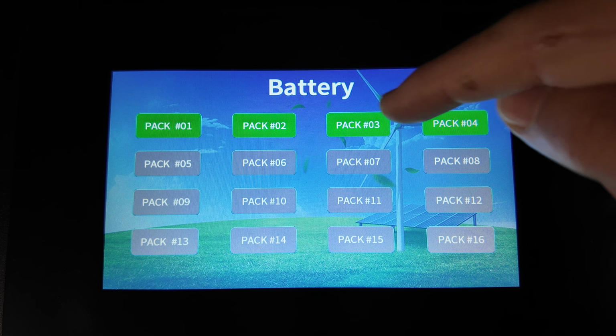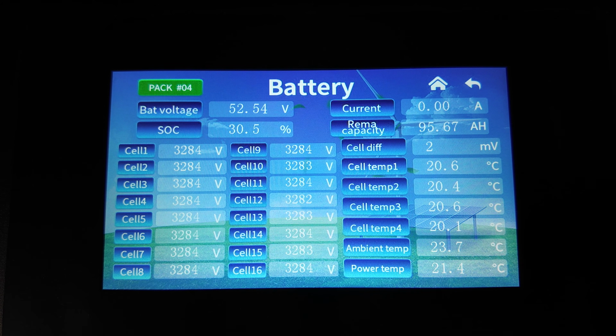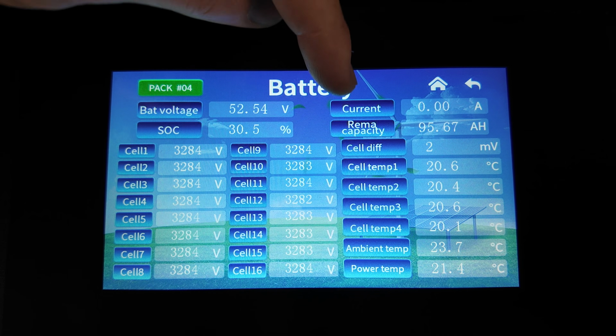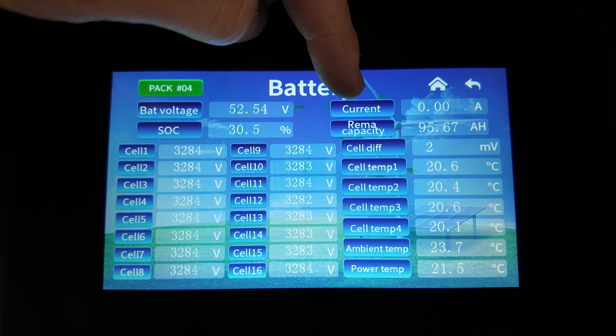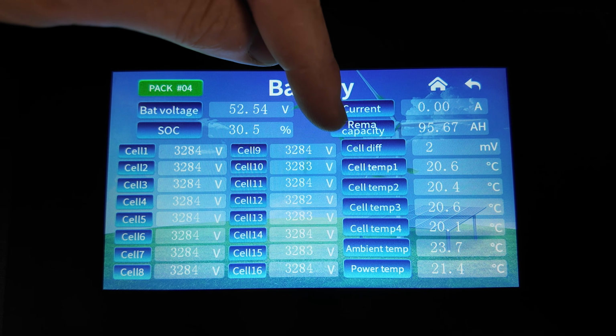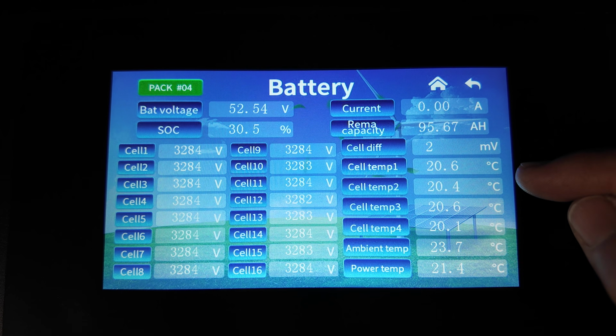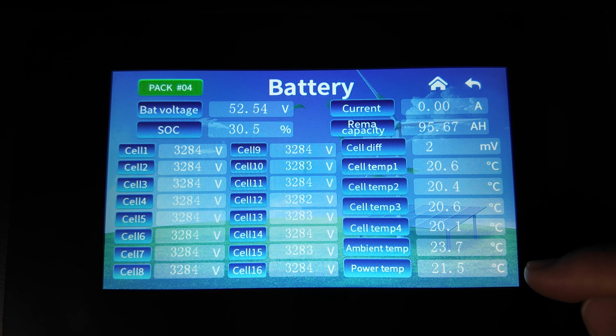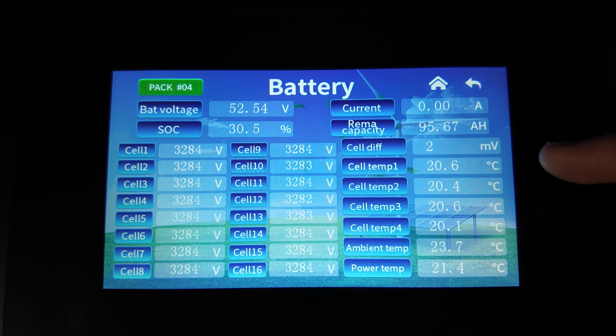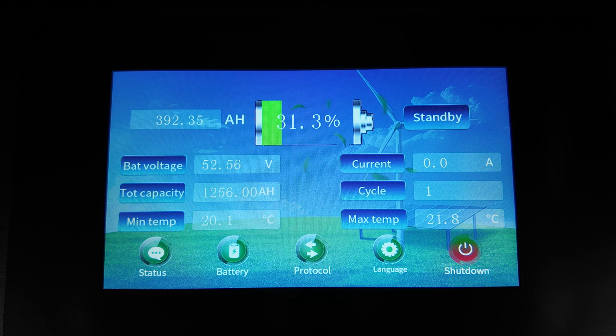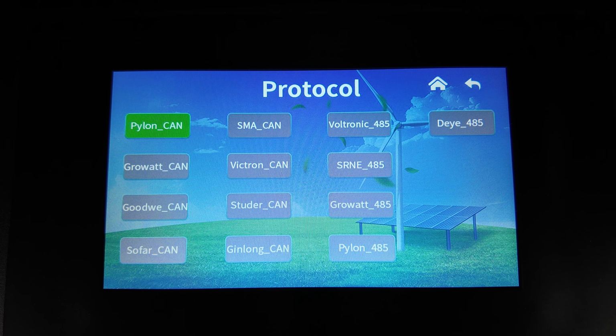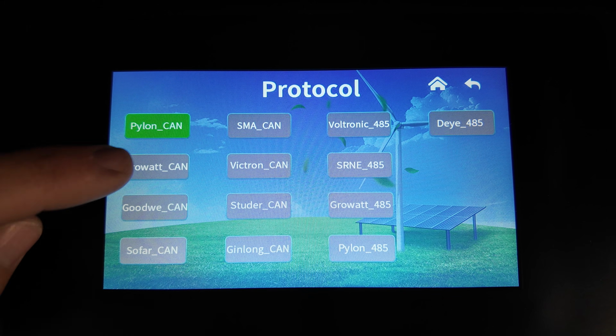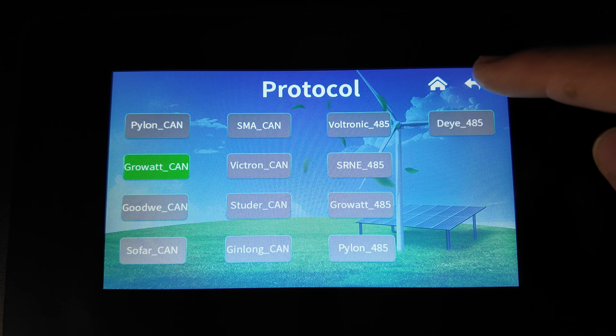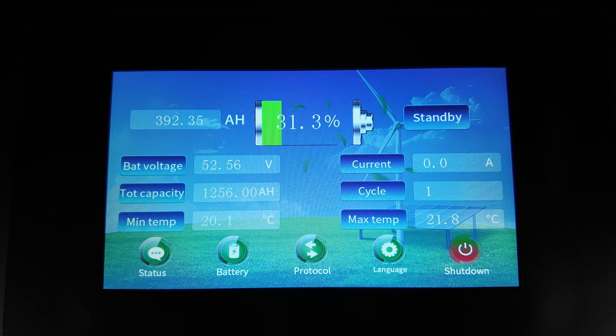Next, we have the battery itself. We will be able to pick again any pack that we like. This is where you're going to see individual cell voltages, individual module voltage, and state of charge. We have the current coming in or out of this pack and remaining capacity of this pack. You'll also see here your temperature differences, ambient temperatures, power temperatures, and cell difference. To set the protocol on the battery, tap the protocol, select the protocol required for your inverter, and then simply exit the screen. Your protocol is set.